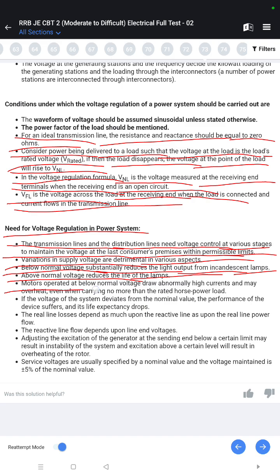Motor operated at below normal voltage draw abnormally high current and may overheat even when carrying no more than the rated horsepower load. If the voltage of the system deviates from the nominal value, the performance of the device suffers and its life expectancy drops. The real line losses depend as much upon the reactive line as upon the real line power flow. The reactive line flow depends upon line end voltages.